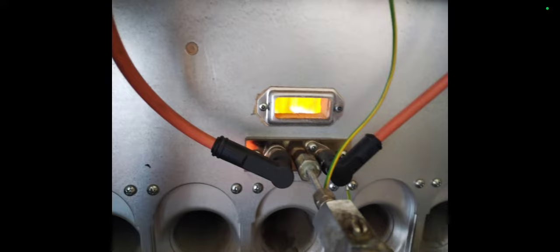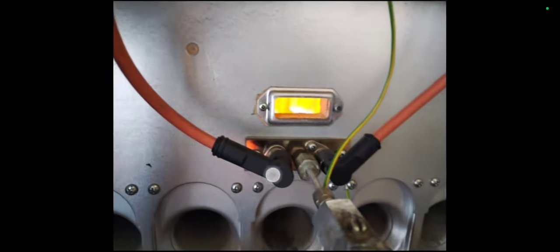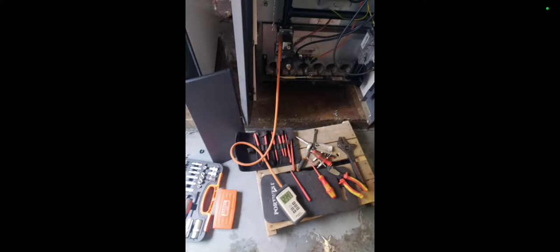Well, I had to make some adjustments on this boiler. There are a few things holding this boiler off, funny enough. What I found, which was quite strange, was that when somebody had worked on it, instead of them isolating it afterwards to say that more work was required, they just left it on. And don't do that. Please practice not to do that. If you're working on something and it's not safe, it's not being fully commissioned, make it quite clear to the person that may come after you to do the work that it's not safe to work on, that certain tests need to be carried out.